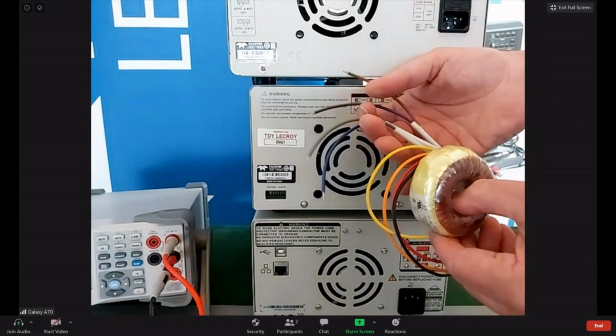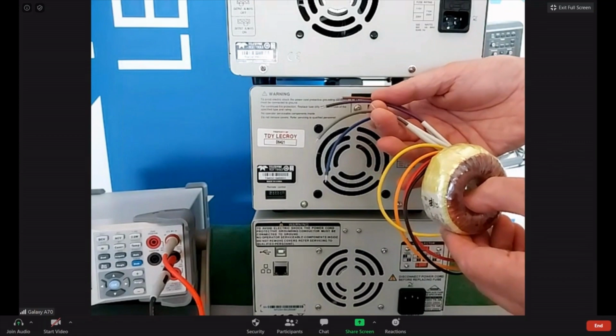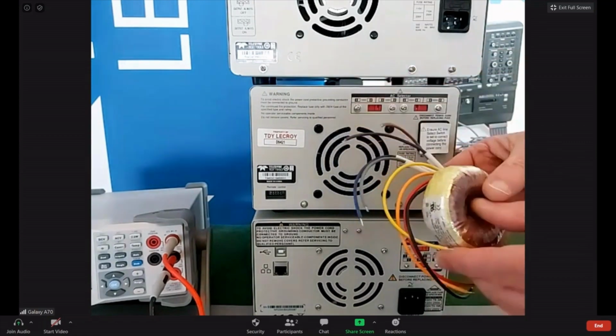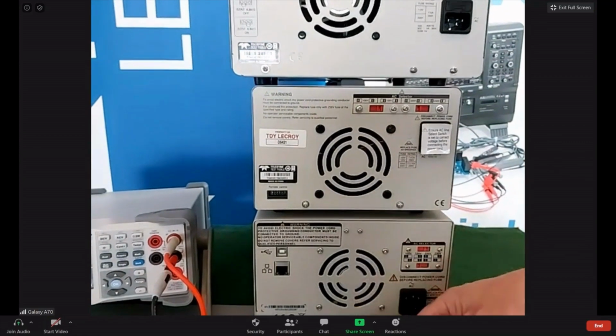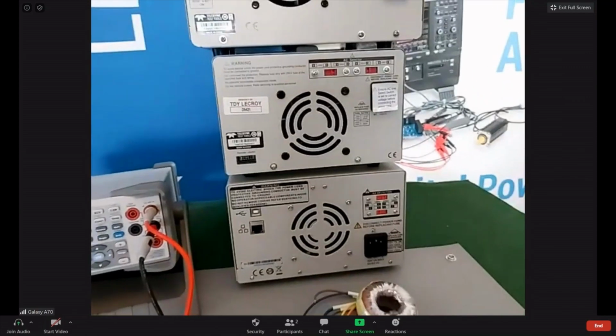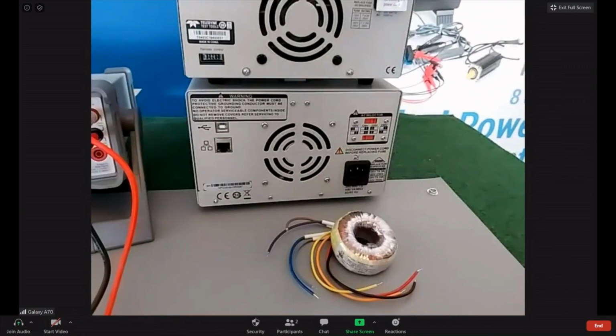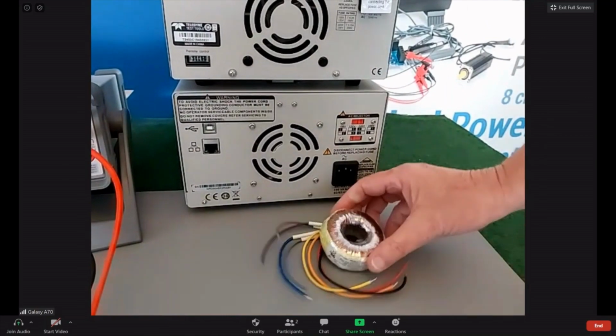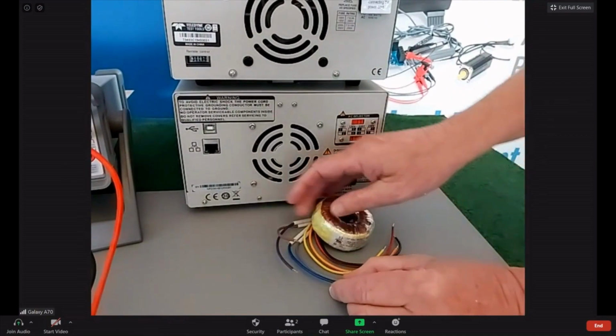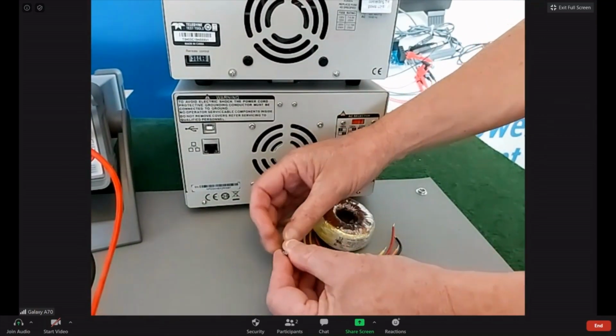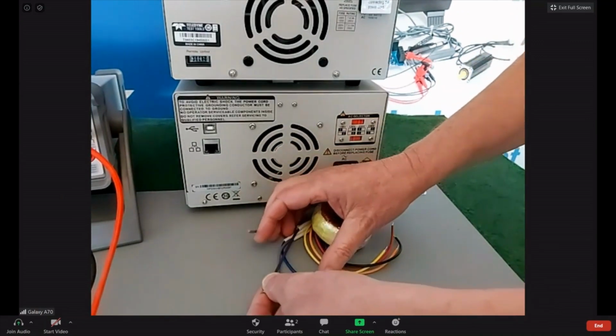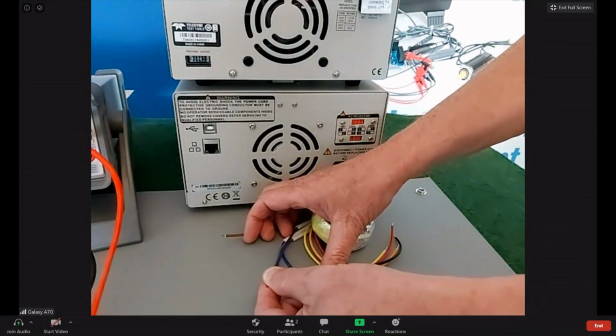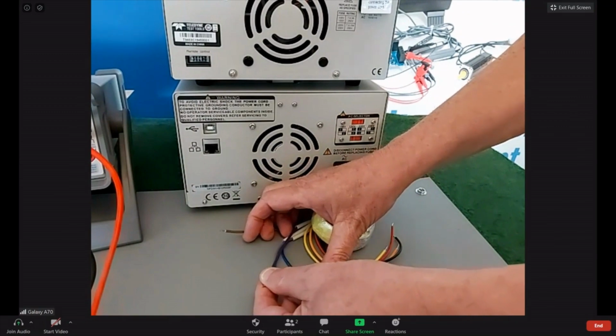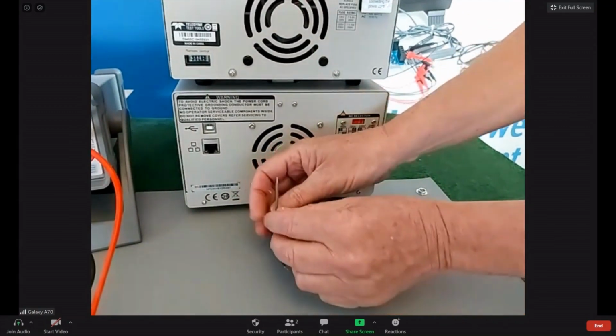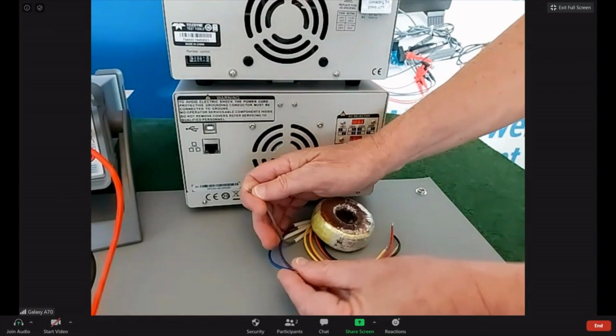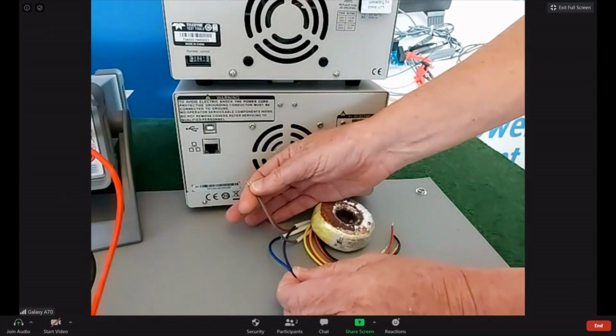If I take these to 115 volts and connect them serially - so my input on blue and brown, connecting these two together - it would be set to 230 volts. Whereas if I connect them in parallel, then I'd have it set to 115 volts.